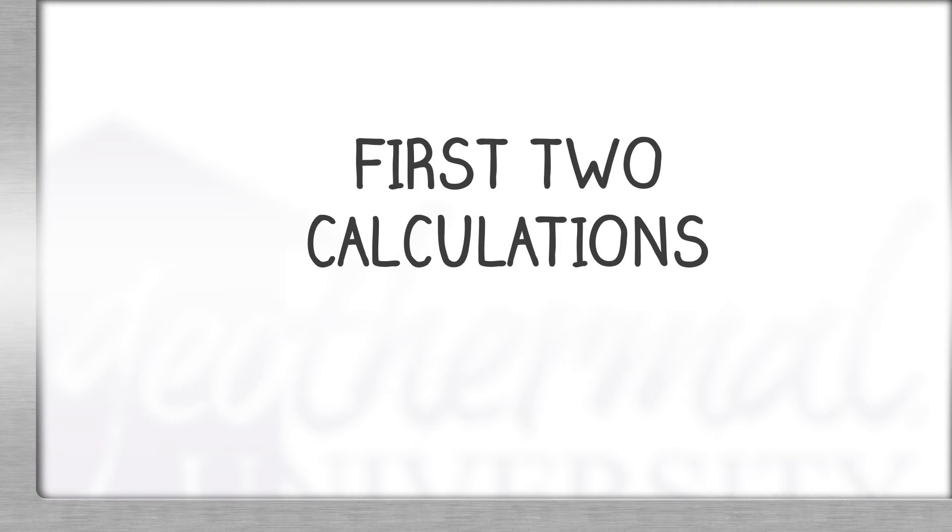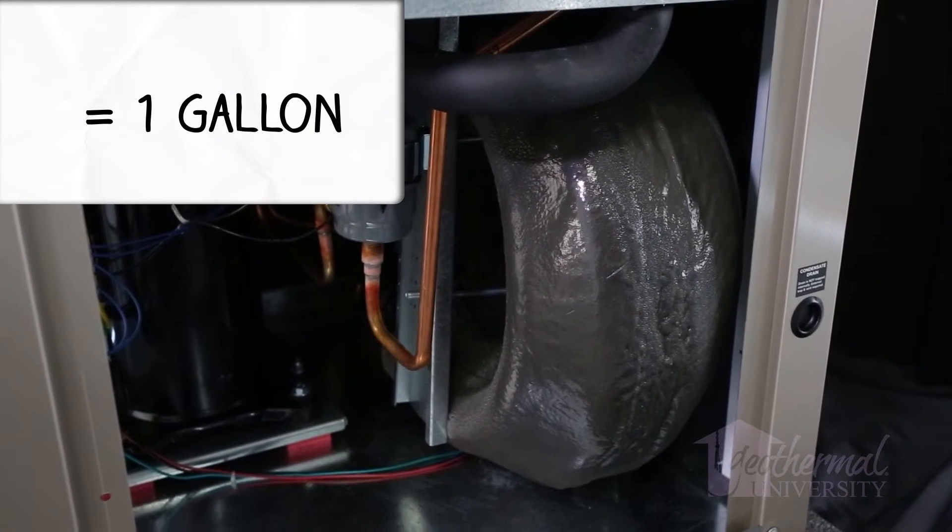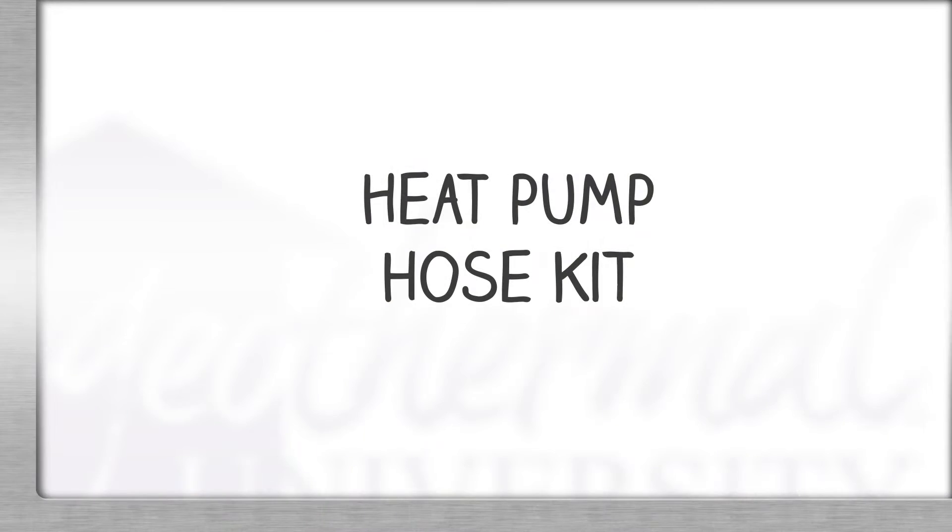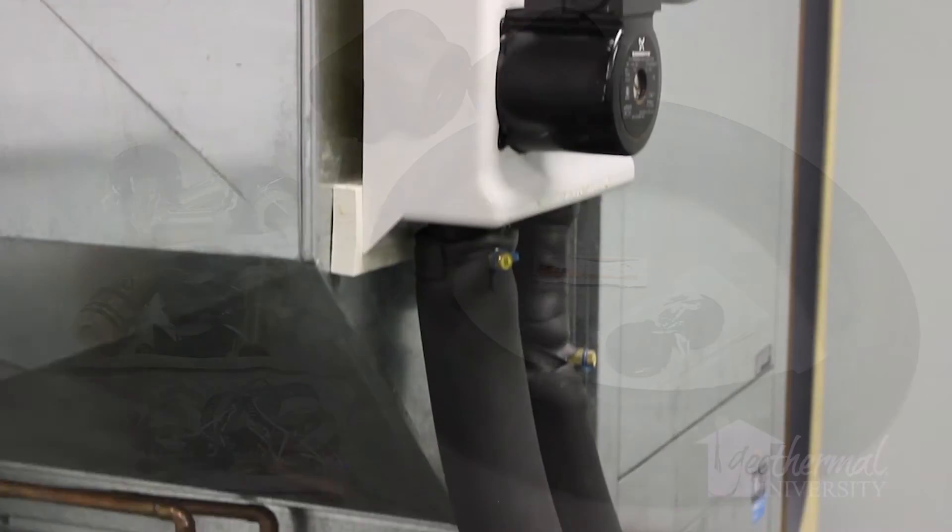Our first two calculations are very simple. In fact, not really calculations, more like standards. For the geothermal coax heat exchanger, use one gallon. Next, we'll allow for the hose kit. The hose kit should not exceed ten feet. A ten-foot hose kit contains four-tenths of a gallon.